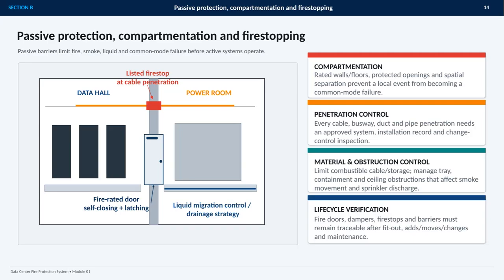This section focuses on passive protection, compartmentation, and fire stopping, the measures that limit fire, smoke, liquid, and common mode failure before active systems can respond. The central idea is containment. A local event should remain local, rather than spreading from the data hall into the power room or across critical spaces. Compartmentation relies on rated walls and floors, protected openings, and adequate spatial separation. Penetration control is equally important.